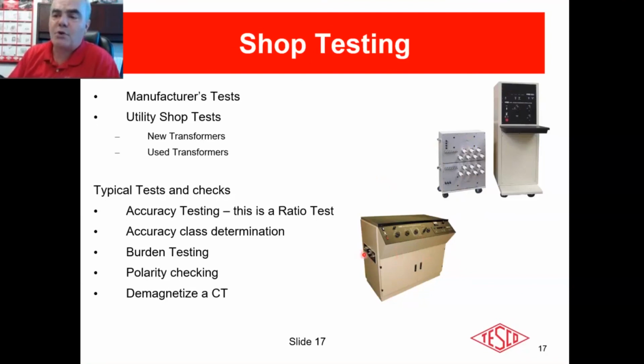The transformer under test hooks up right over here, and inside of here is a precision transformer and a loading transformer. That particular precision transformer has a feature that allows you to test it against itself every day, just to do a sanity check to make sure that everything is still working correctly. So it basically splits in two, measures against itself, and should always come back 100% accurate. All right, so it's called a self-test. Once again, this is a highly precise transformer. We have ones in our lab that are directly traceable back to our international standard. And as far as we know, as I said, there's nothing more accurate than either of these.